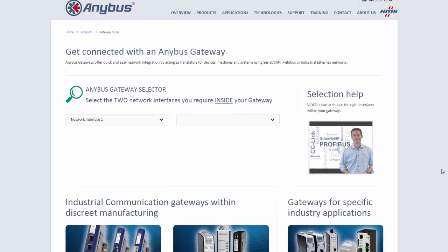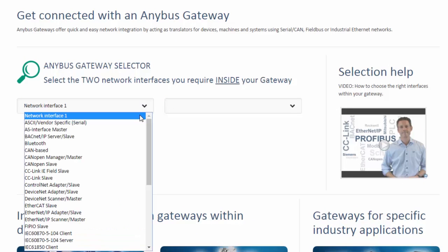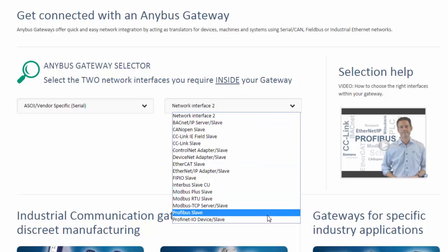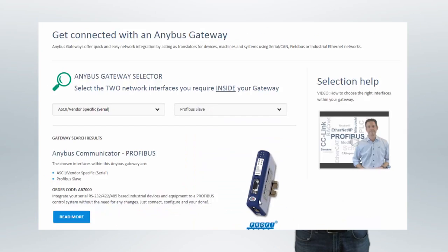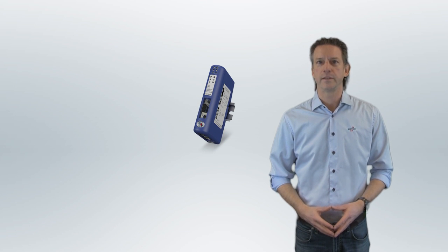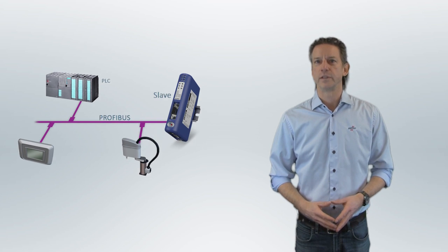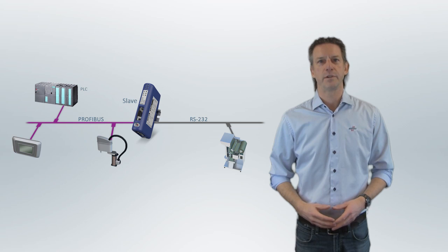If you want to connect a serial or CAN-based device to a network, simply select your subnetwork interface first and then the industrial network you want to connect to. You will get the correct gateway for this combination. In this example, the solution was an Anybus Communicator which will act as a slave on the Profibus network, translating information to and from the serial device.